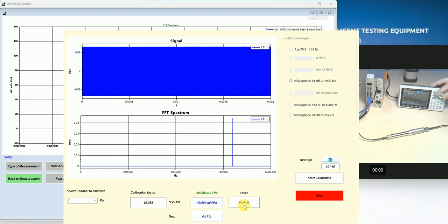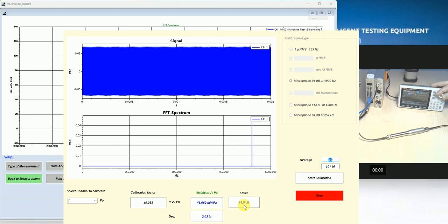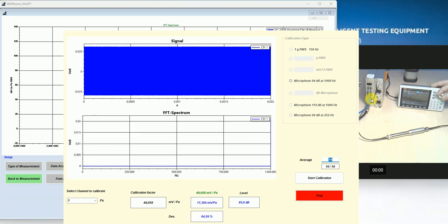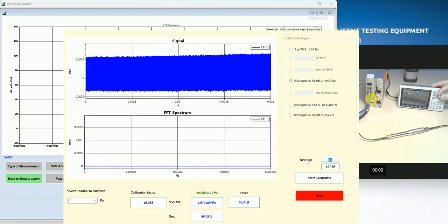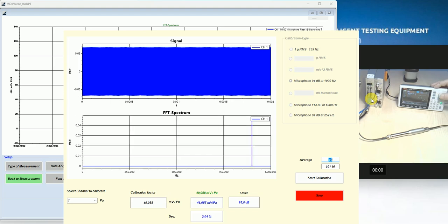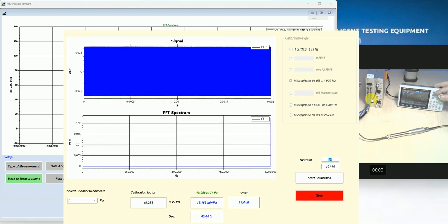Now I'm at 800 kHz. And now we can see that from 94 dB it goes down to 93.8. This is the point where the anti-aliasing filter from the LTTsmart is active. If I go to higher frequency, we see strong damping. Now again back. Okay.